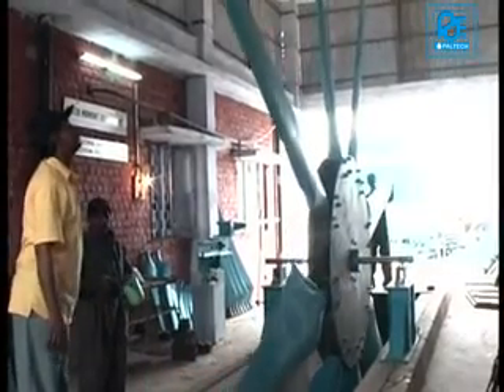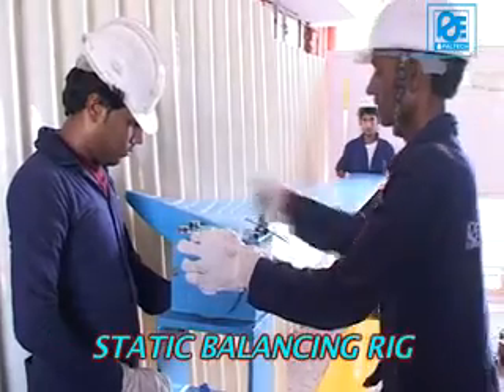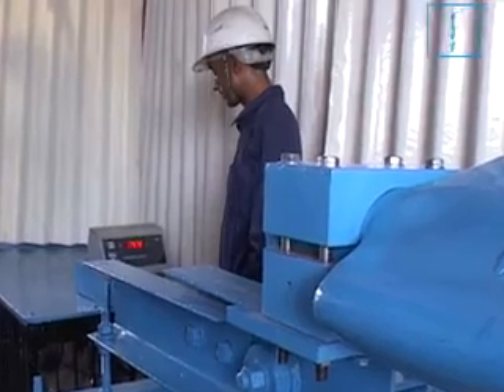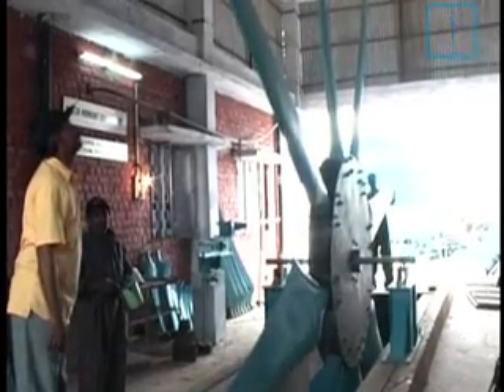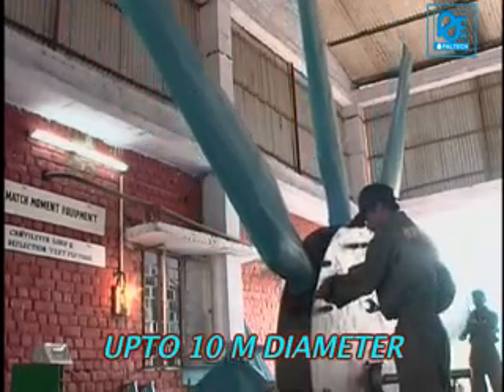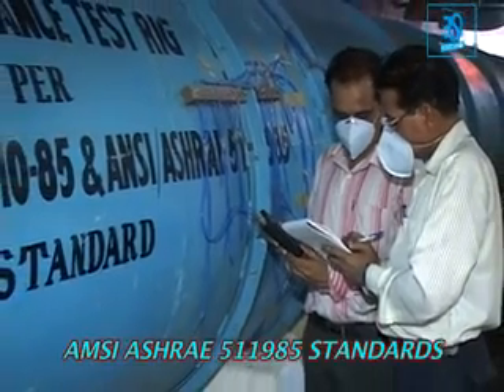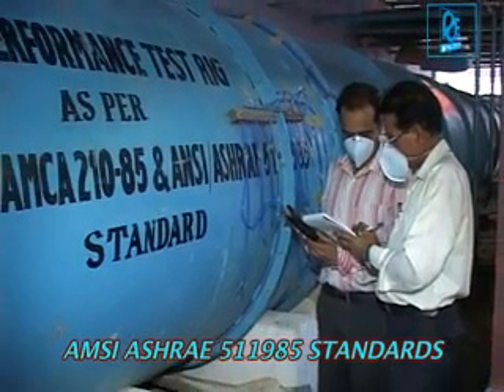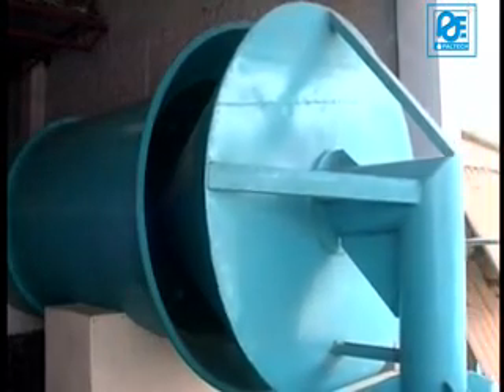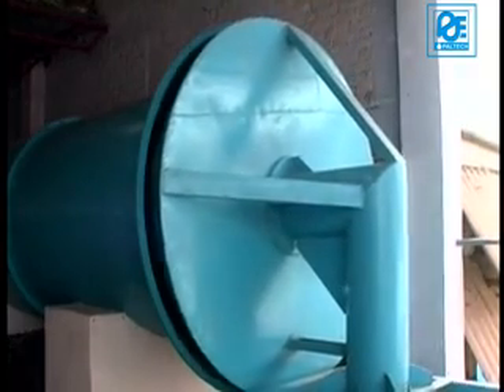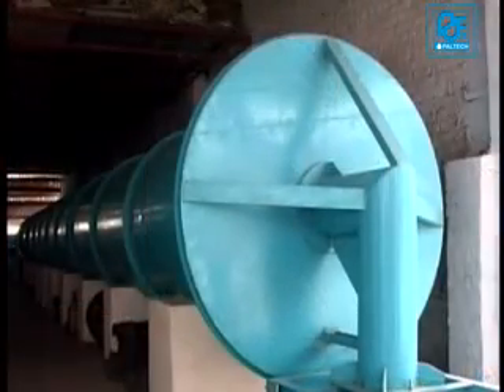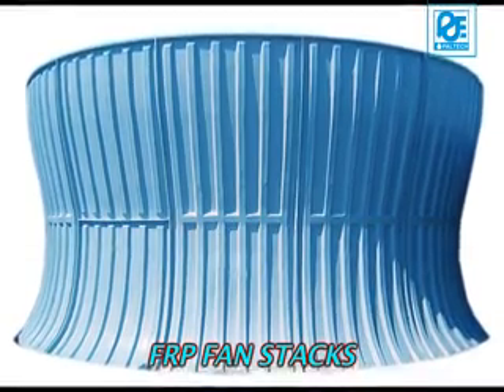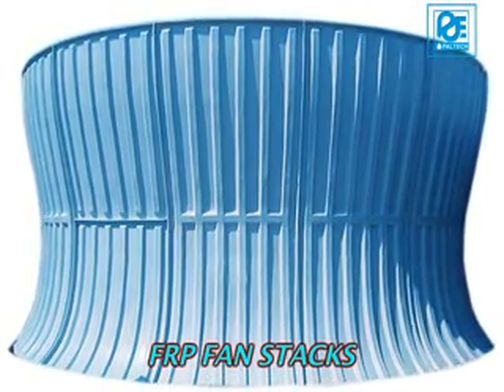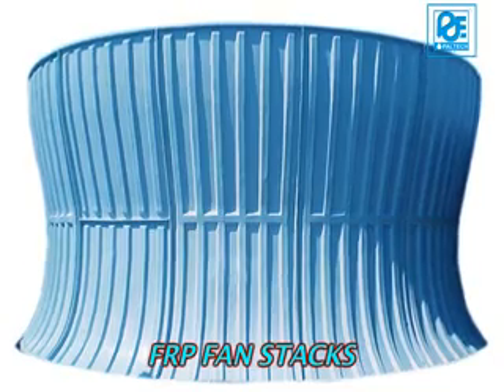The dynamically balanced hub and match moment blades are put on static balancing rig and are checked for any imbalance and corrected. Paltech has created one of India's largest static balancing rig for fan assembly up to 10 meter diameter. The testing facility is as per ANSI AMCA 210-85 and ANSI ASHRAE 51-1985 standards. The facility is upgraded with various diverging and converging tunnel sections to make it possible to test various fan sizes. Paltech manufactures high efficiency velocity recovery type GRP strong and heavy duty fan stacks.